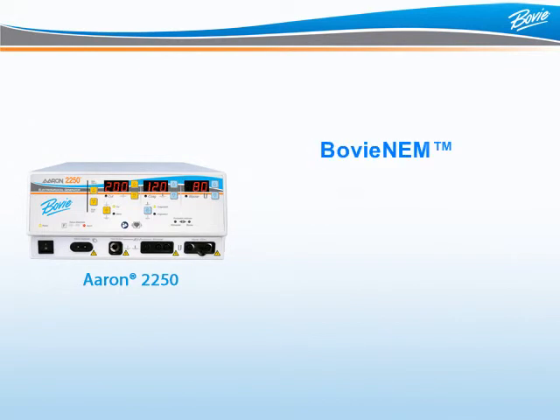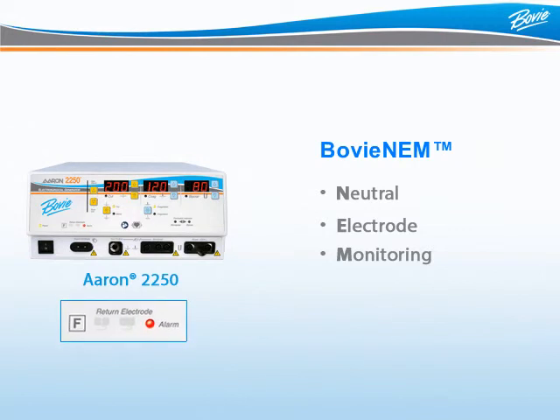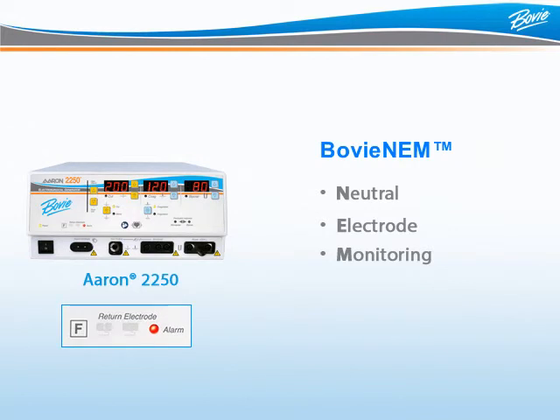BovieNEM, or Neutral Electrode Monitoring, means the generator is consistently checking to ensure that the grounding pad is properly connected to the patient when using disposable split pads, reducing the risk of patient burns. If during the procedure there is a loss of contact, the Aaron 2250 will alarm and the unit will disable until the grounding pad is properly connected once again. This feature is only available when a disposable split pad is used with the generator.